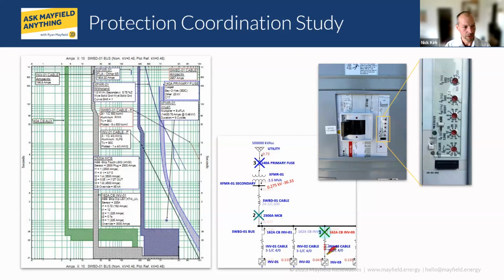And once we've got that all built and coordinated, we can then verify it, like Victor showed earlier, by inserting a fault in a particular location. In this instance, I inserted one just on the line side of inverter 3, and you can see that the first overcurrent protection device to trip was indicated there by the 1. That's the 162 amp circuit breaker, and then it went upstream from there. So the first one isolates the fault, but if for some reason that were not to interrupt, then it would follow upstream of the fault.